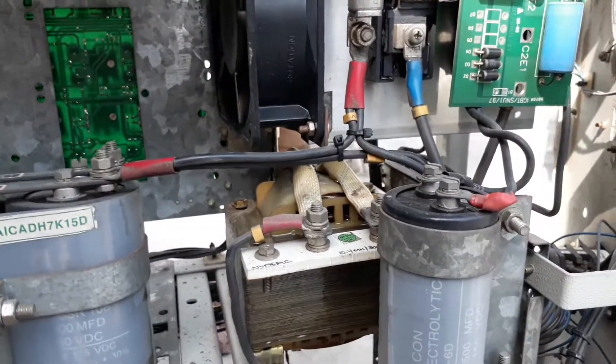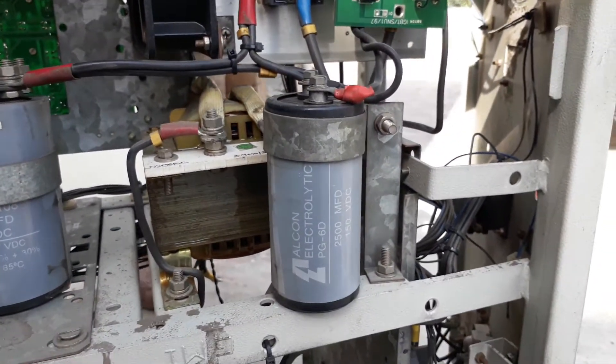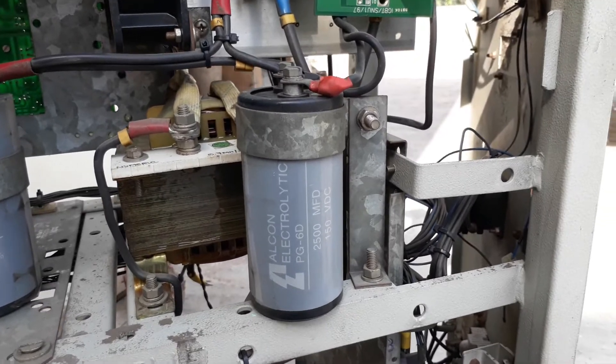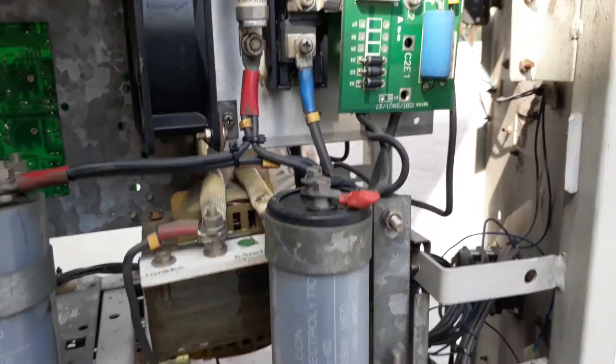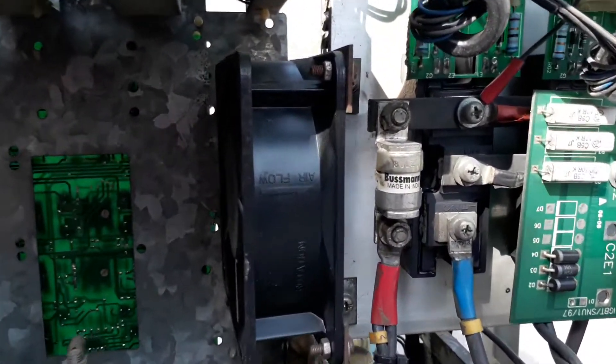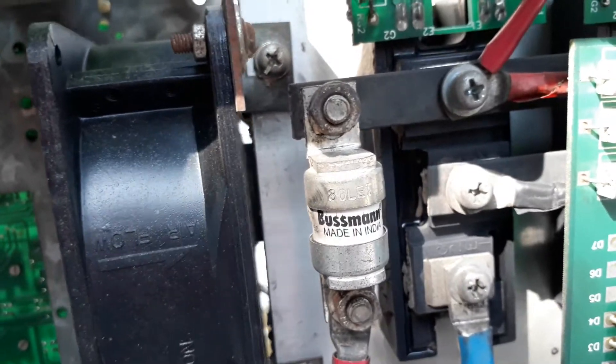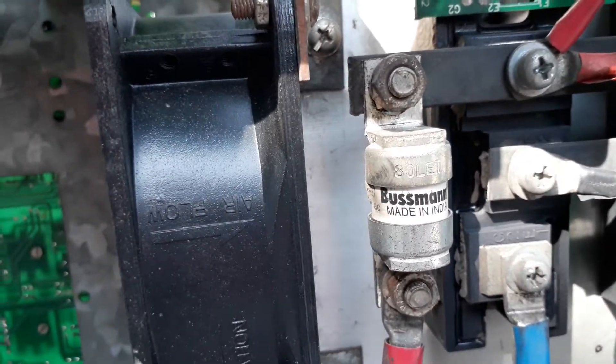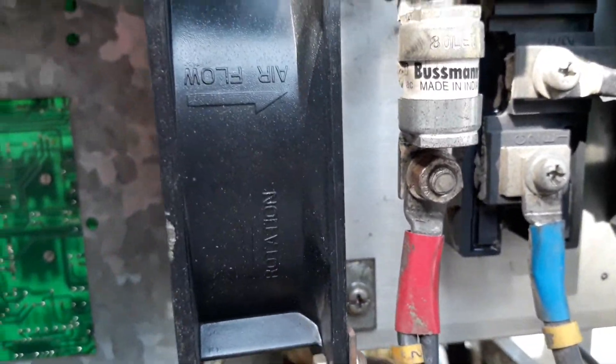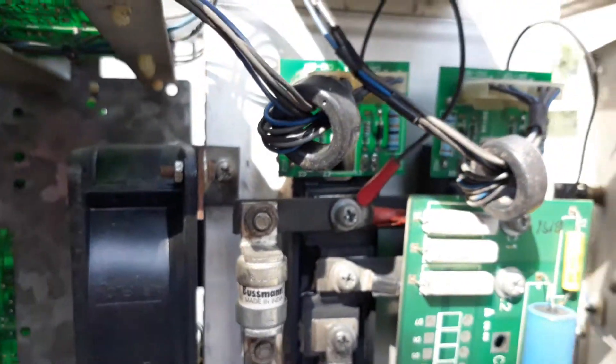And also this is a DC filter attached to this IGBT through this HRC fuse. You can see, Bussmann made, it's around 80 amperes. These are the IGBTs.